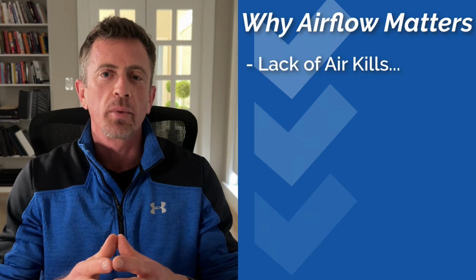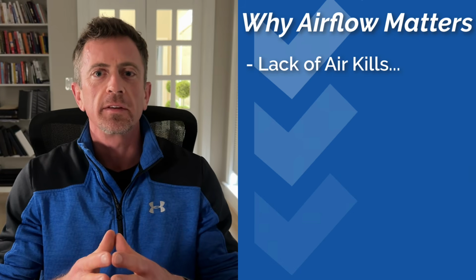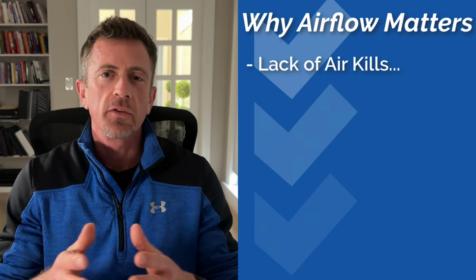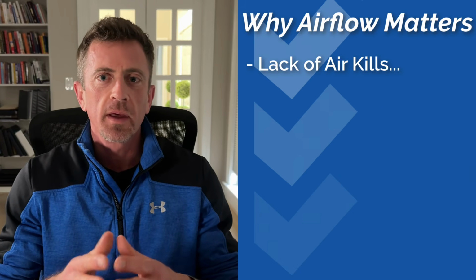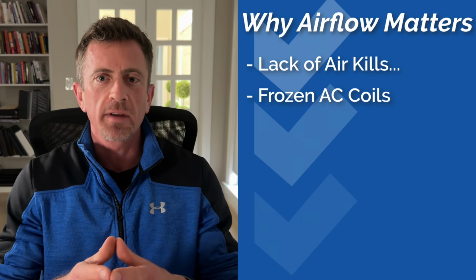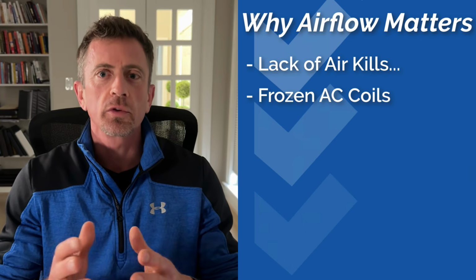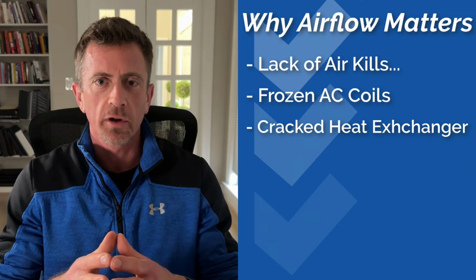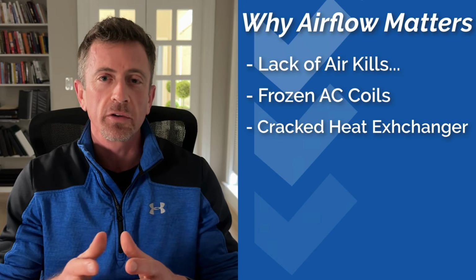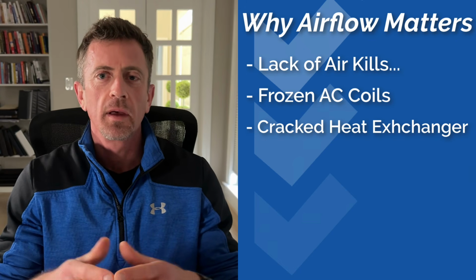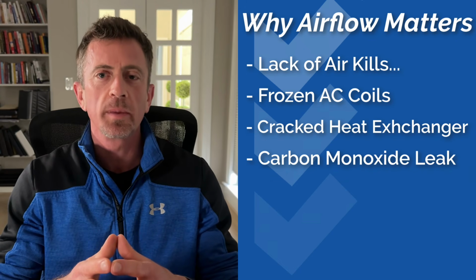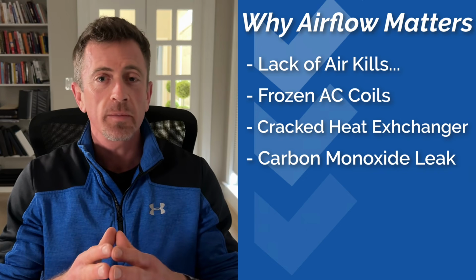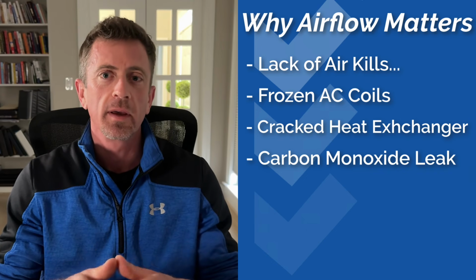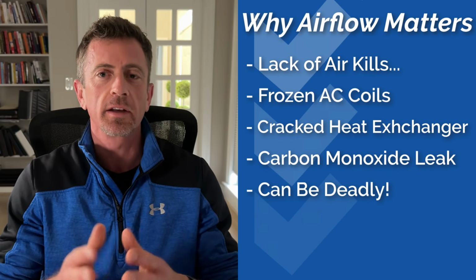Here's where it gets really important. Low airflow can lead to some serious problems. If your AC doesn't get enough airflow, the AC coil can actually freeze up, and with gas furnaces, restricted airflow can cause the heat exchanger to overheat and crack, which is a major safety hazard. A cracked heat exchanger can leak carbon monoxide into your home, and that's something you absolutely do not want to happen, as it can be deadly if it's left undetected for too long.